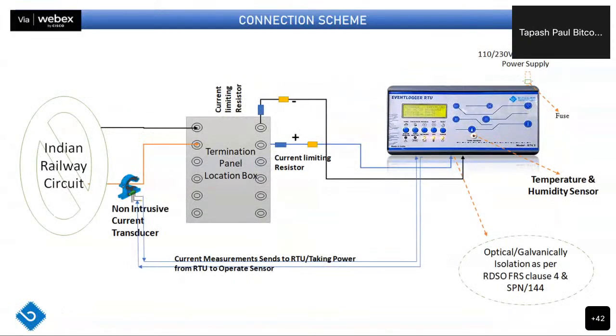So the connection scheme shows how we are connecting and measuring voltage. This is just an example. On the left side we can see an Indian Railway circuit, and on the right side we take the input from the Indian Railway circuit to our device for monitoring. For voltage measurement, direct tapping is done from the railway termination panel in the location box, going to the device, and this voltage measurement is galvanically or optically isolated.